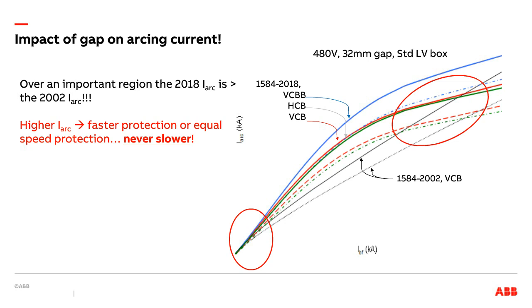There is a characteristic of the two that is very important and actually sort of facilitates the process I'm going to describe. And the fact is that generally speaking, in the new model, for a VCB, HCB, or VCBB, i.e. vertical electrode, horizontal electrode, or vertical electrodes into a barrier, the arcing current will be higher than what the old study would have predicted.